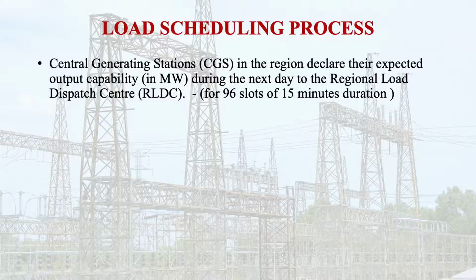Now we describe the load scheduling process. What is this load scheduling process? It starts with the central generating stations, also called CGS, because the generating station is the station which gives power to the load. When the process starts, the central generating stations in the region have to declare their expected output capacity in megawatts for the 96 slots of 15 minutes duration during the next day to the regional load dispatch centers.